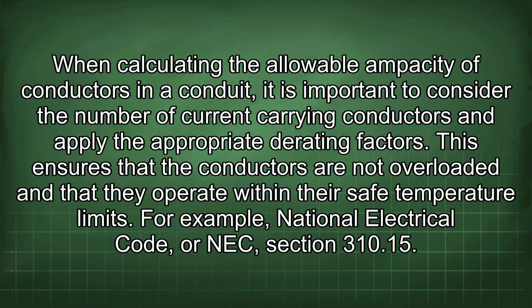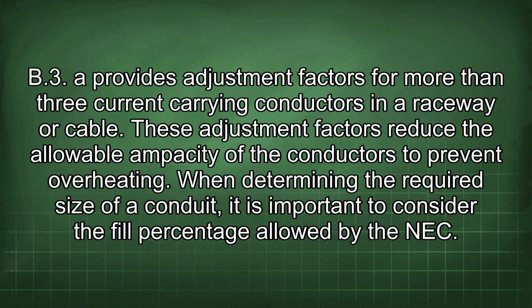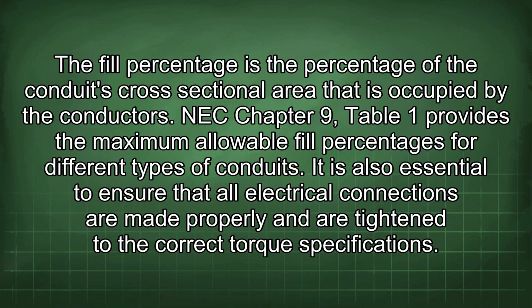For example, National Electrical Code, or NEC Section 310.15(B)(3), provides adjustment factors for more than 3 current-carrying conductors in a raceway or cable. These adjustment factors reduce the allowable ampacity of the conductors to prevent overheating. When determining the required size of a conduit, it is important to consider the fill percentage allowed by the NEC. The fill percentage is the percentage of the conduit's cross-sectional area that is occupied by the conductors. NEC Chapter 9, Table 1 provides the maximum allowable fill percentages for different types of conduits.